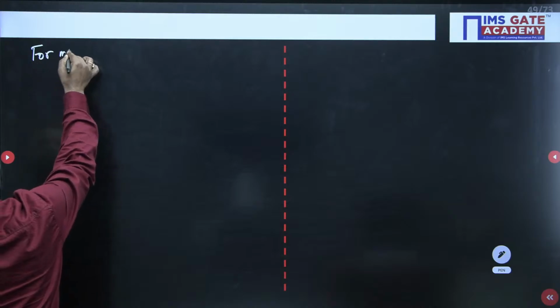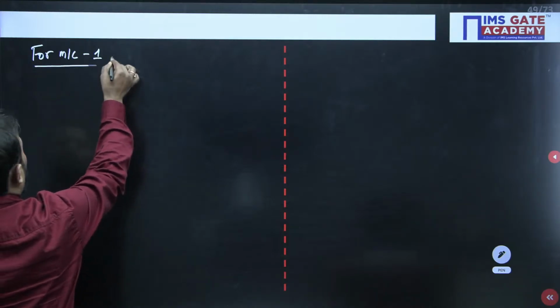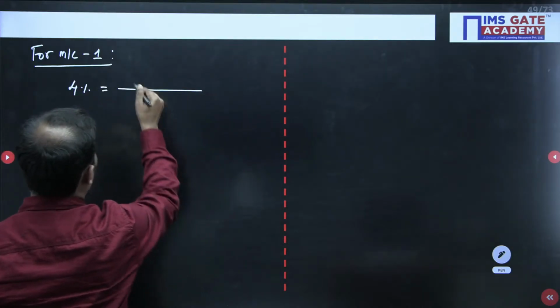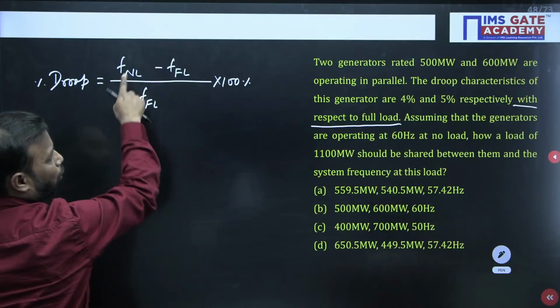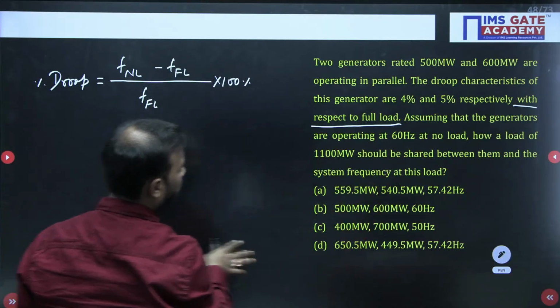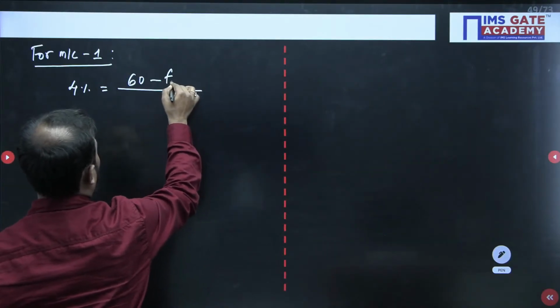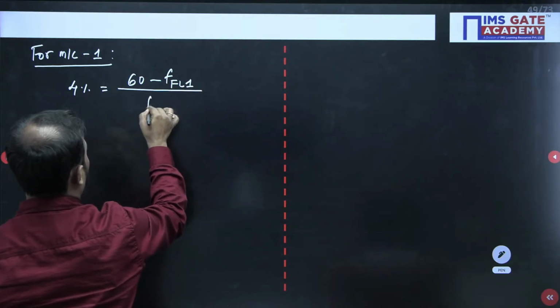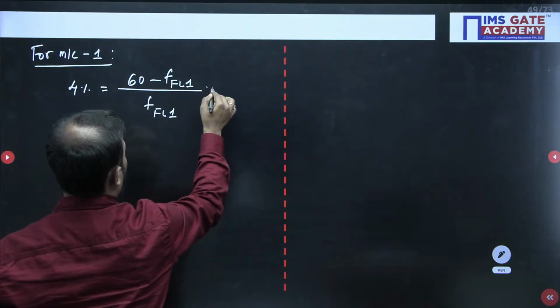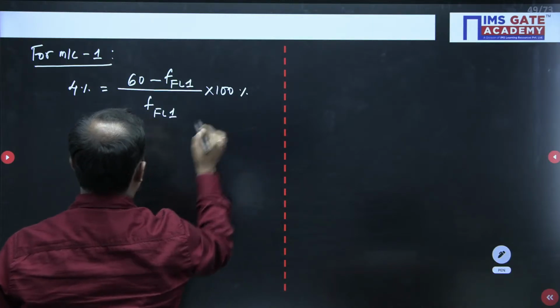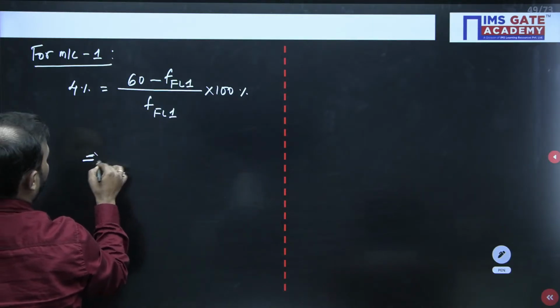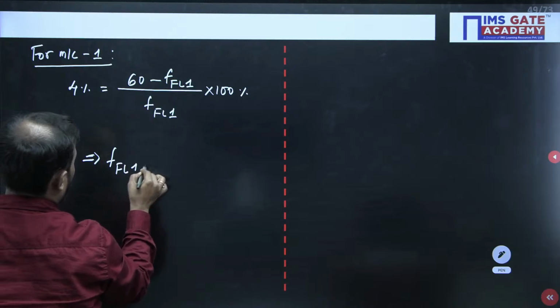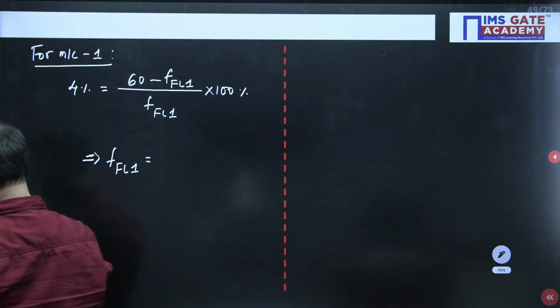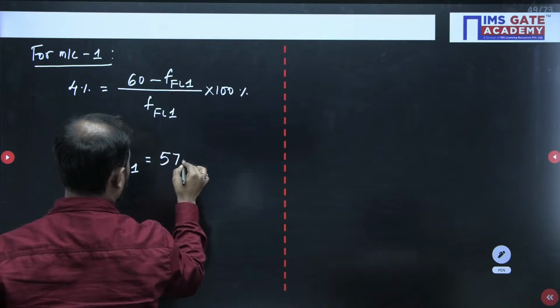Okay, so for machine 1, 4% droop, which is equal to no load frequency, which is 60, minus F full load 1, divided by F full load 1, into 100%. So let me write it directly: frequency at full load, this value is 57.7 hertz.